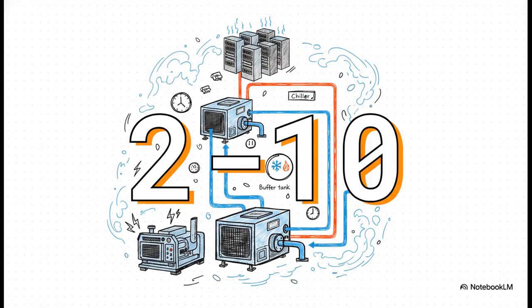Okay, let's dive right into this. 2 to 10 minutes. That right there is the crucial window. Now, you might be thinking, hey, in a world-class data center, if the power flickers, the backup generators just instantly kick in and everything's totally fine, right? Well, kind of. The electrical power might be fine, but the cooling? Totally different story. You see, even when those massive emergency generators turn on, the heavy-duty chillers that actually produce the cold water for the whole facility need to go through an intricate safety sequence just to restart. They have to protect their internal motors, they've got to stabilize their oil pressure, the whole shebang. Because of this, it takes a bare minimum of 2 minutes and sometimes up to 10 whole minutes for a chiller to fully reboot and actually start supplying cold water again.